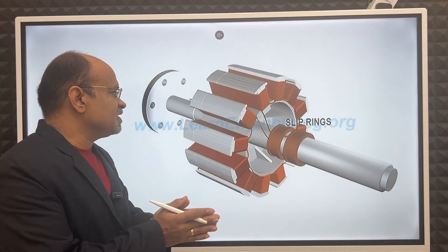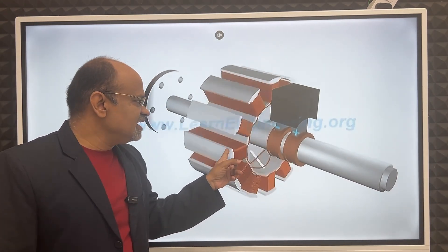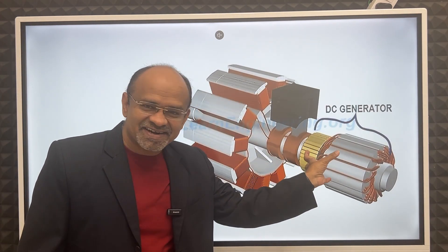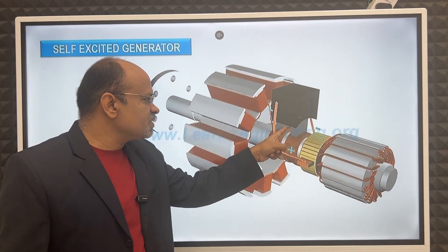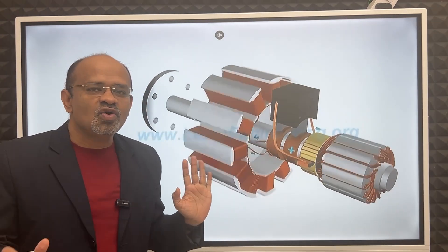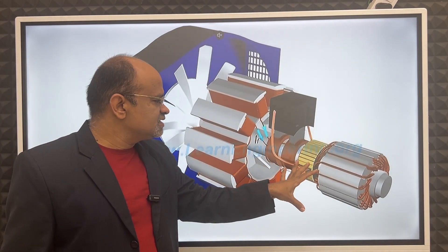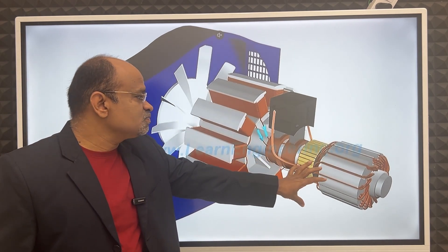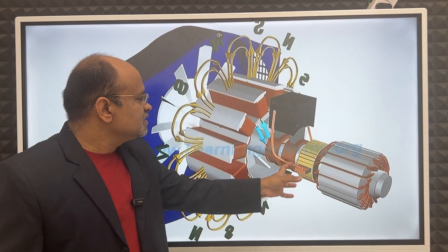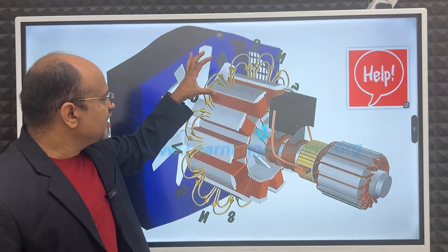Slip rings are required to supply current to the rotor coils. A small DC generator — called a self-excited exciter — feeds current via brushes that slip on the slip rings, passing current to the rotor coil and providing excitation. This is the Automatic Voltage Regulator (AVR): by increasing or decreasing the excitation voltage, we regulate the output voltage of the generator.